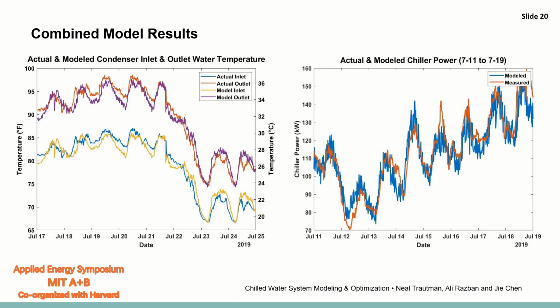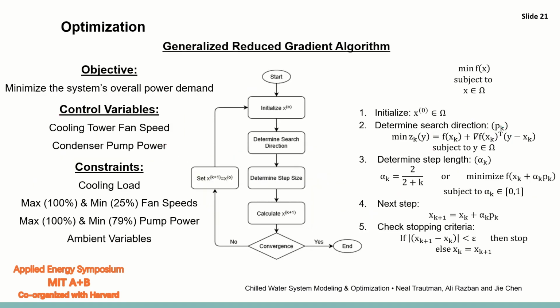And using these relationships, we were able to determine the relationship between the actual and modeled inlet and outlet condenser water temperature. You can see the graph of those on the left. They follow similar patterns. And on the right is a relationship between the actual and modeled chiller power for a period of time during the data collection process, which also follows similar patterns. And that brings us to how we optimize the system.